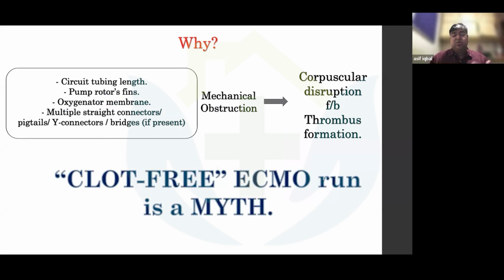At that time what we do is increase the flow. If you increase the flow, the chance of clotting is less. So you have to increase the RPM of the centrifugal machine to increase the flow, and you have to maintain good hydration of the patient to reduce the viscosity of the blood.